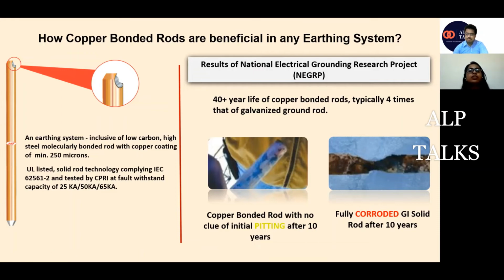Talking about the life of this material, there is a study conducted by the National Electrical Grounding Research Project. They took a 14 mm GI solid rod and a copper bonded steel rod of the same size, and buried them for 10 years. After 10 years, when they excavated those pits, they found that the GI rods were fully corroded, whereas the copper bonded rods showed no sign of initial pitting. So they concluded that copper bonded rods have a life of 40+ years as compared to GI solid rods. For example, with respect to the fault current, 25 kiloamps, 50 or 65 kiloamps.